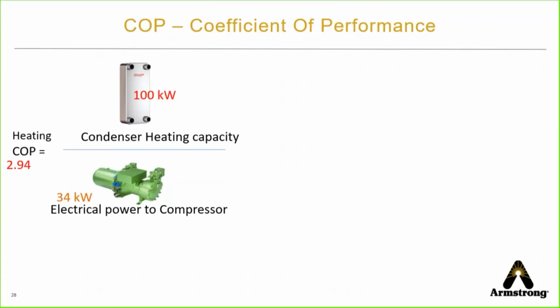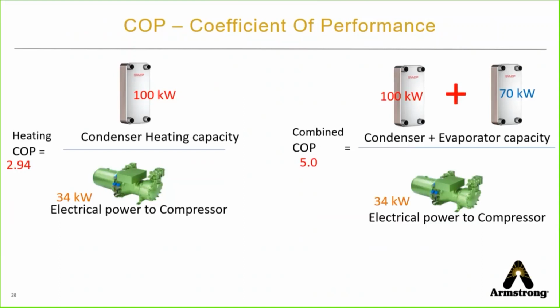That alone, if we're taking advantage of just the heating portion of the heat pump, will give us a COP of roughly 3, or 2.94. If I take a look at that then and say I'm going to use both the heating side and the cooling side, that same 34 kilowatt of electricity input will deliver that 100 kilowatt of heat energy out, the hot, but also deliver to us 70 kilowatts of cooling. So a combined 170 kilowatts of heating and cooling energy, or a combined COP of 5.